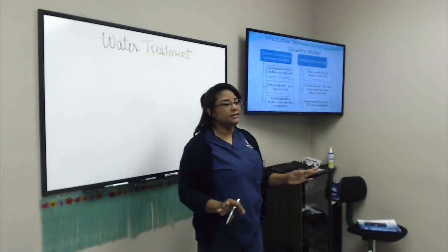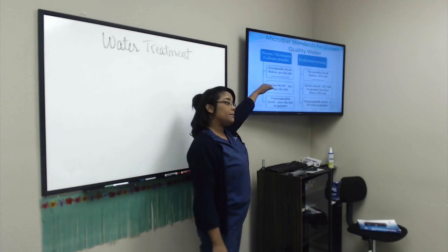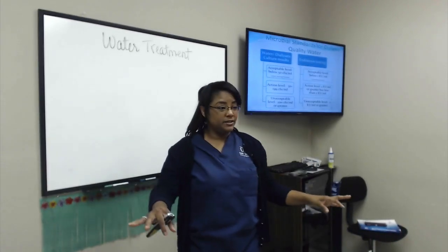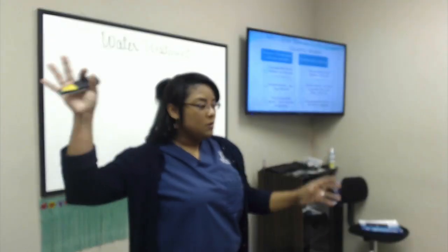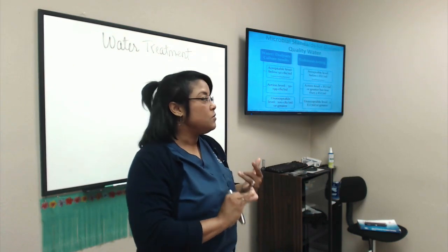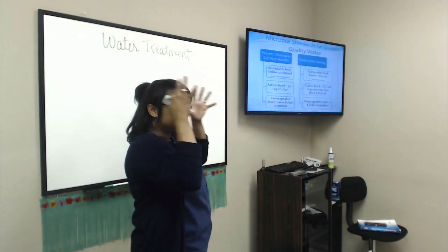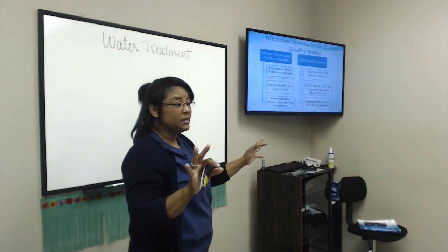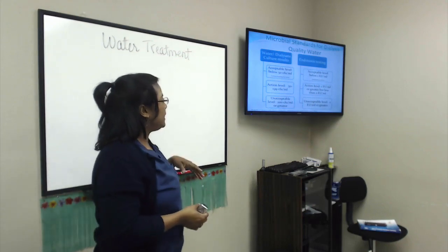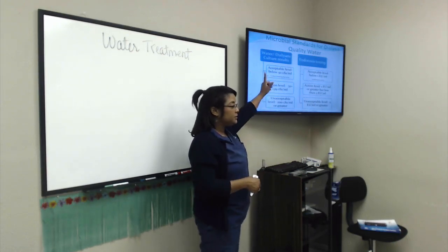We're gonna perform dialysis as usual. Action level, here we can finish today's operation, but before tomorrow, we gotta disinfect everything. So we gotta disinfect the pipes. We gotta empty the water that's in the container. We gotta disinfect machines, everything before tomorrow, okay? So again, action level, we are able to finish with today's operation, but we need to have some type of action before tomorrow.